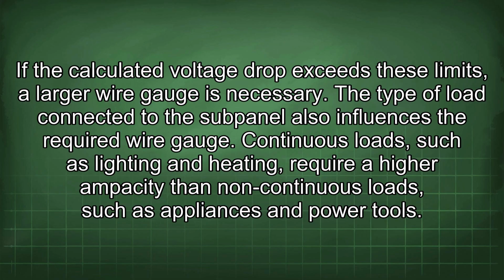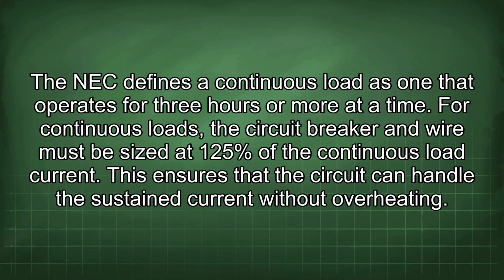The type of load connected to the subpanel also influences the required wire gauge. Continuous loads, such as lighting and heating, require a higher ampacity than non-continuous loads, such as appliances and power tools. The NEC defines a continuous load as one that operates for 3 hours or more at a time. For continuous loads, the circuit breaker and wire must be sized at 125% of the continuous load current. This ensures that the circuit can handle the sustained current without overheating.